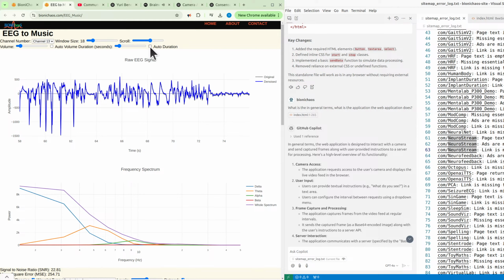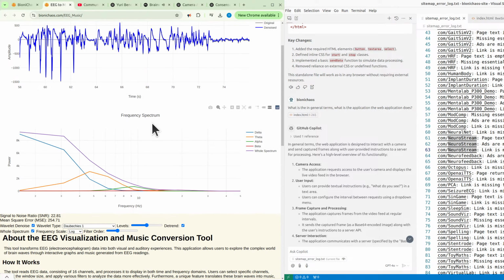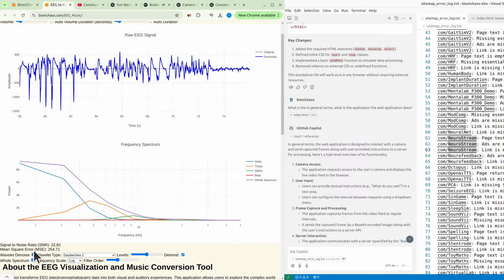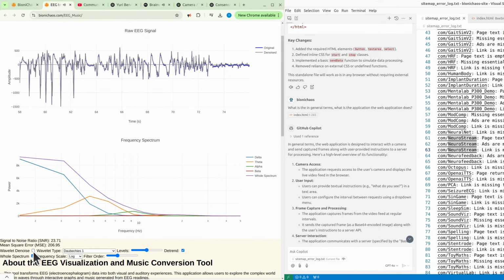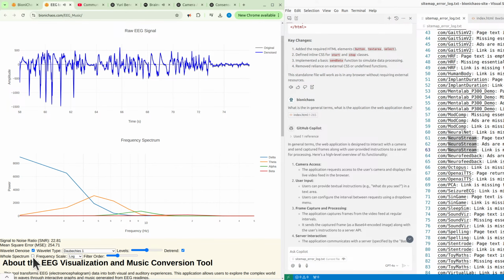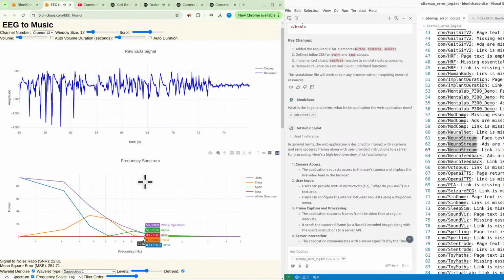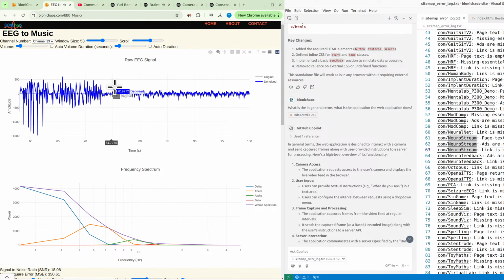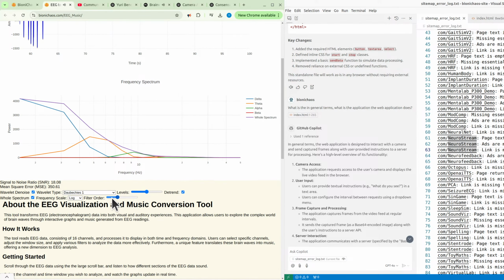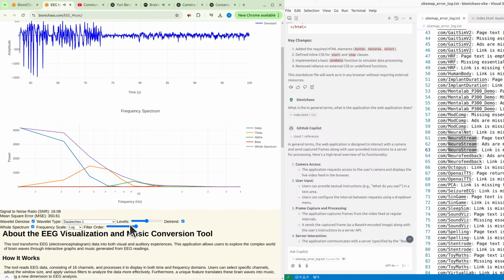And for even finer control, technically speaking, there are filters. You've got a wavelet and noise filter that helps clean up the raw signal, reduce artifacts. Which is crucial for EEG. Definitely. And then there's a bandpass filter. Now, this is like tuning a radio, right? But here you can adjust the filter order from 1 to 4. What does increasing that order actually achieve, technically? Okay, so a higher filter order gives you a sharper cutoff. It means the filter is more effective at isolating just the frequency band you're interested in and rejecting everything else outside that band. So it's more precise, like a finer sieve. Exactly. A higher order filter is more selective.